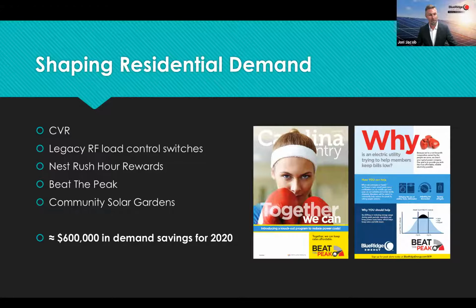We also operate some legacy radio frequency load control switches that are pretty old, from the early 80s. They're not making parts for the control boards that we send a signal to these switches with. They're equipped on AC units and water heaters throughout our service territory, and we're just trying to wring the last little bit of juice out of that program. It's fairly effective, cycling the water heaters and air conditioners on and off in 15-minute intervals.